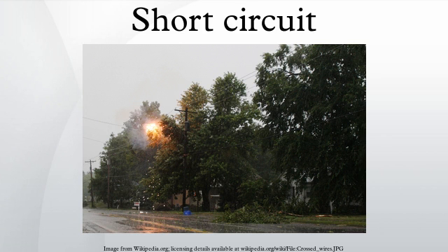Overloaded wires can also overheat, sometimes causing damage to the wire's insulation, or a fire. High current conditions may also occur with electric motor loads under stalled conditions, such as when the impeller of an electrically driven pump is jammed by debris. This is not a short, though it may have some similar effects.